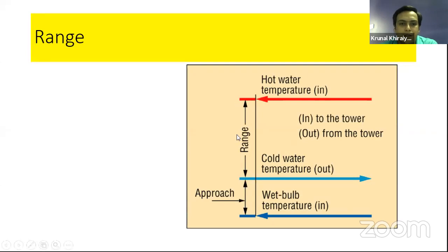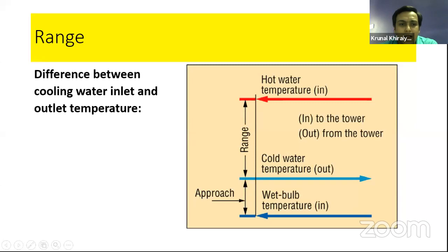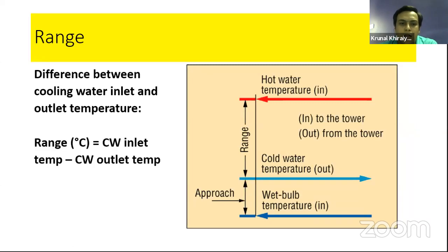So what is range? It is shown in the figure. The range is the difference between the cooling water inlet temperature and the cooling water outlet temperature. And if you have a high range, then definitely, because it is a performance parameter, after measurement of a performance parameter you need to conclude some things. So what is the conclusion from the range? If your cooling tower has a high range, then we can say that it is a good performing cooling tower.